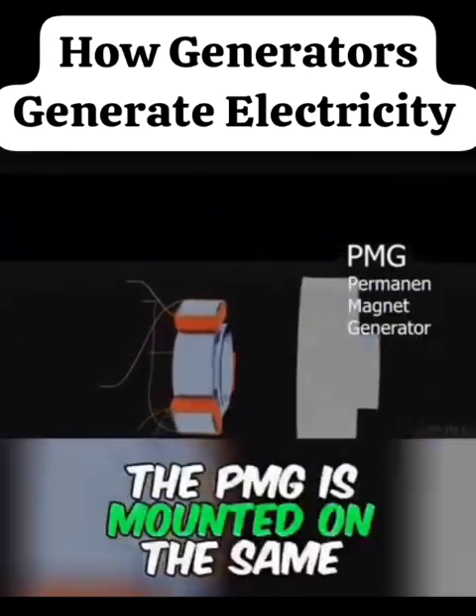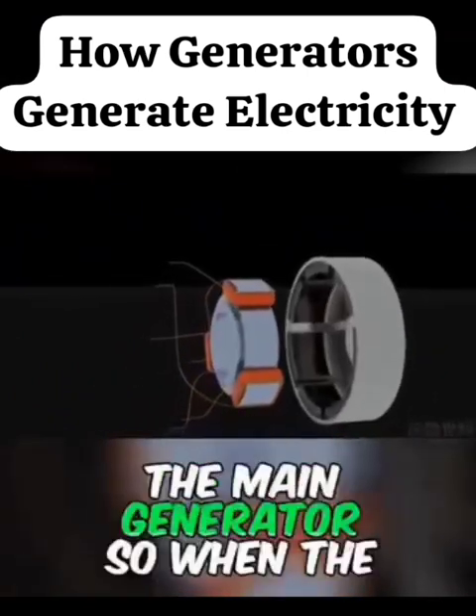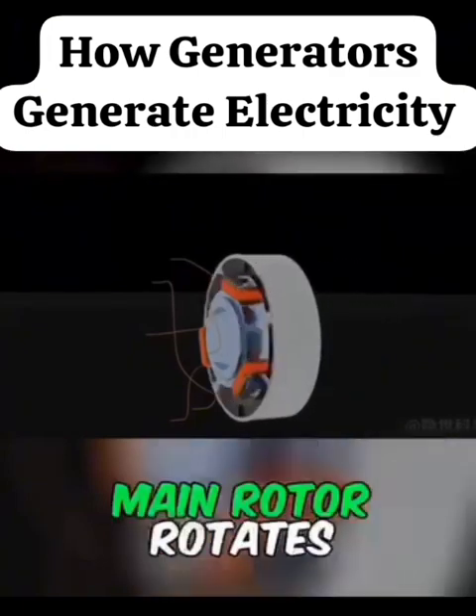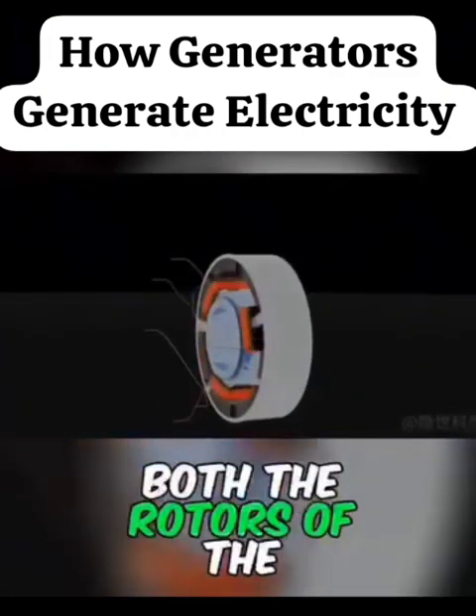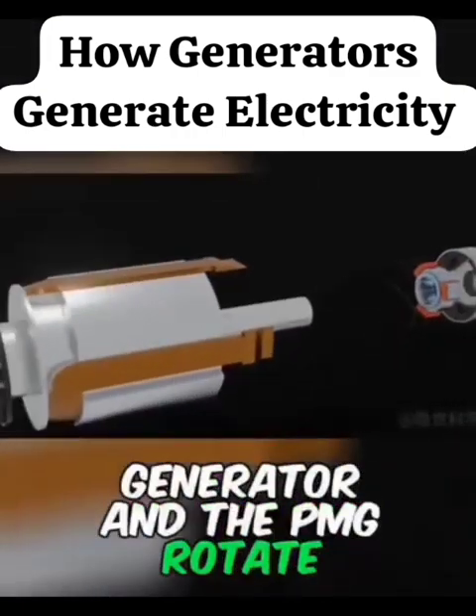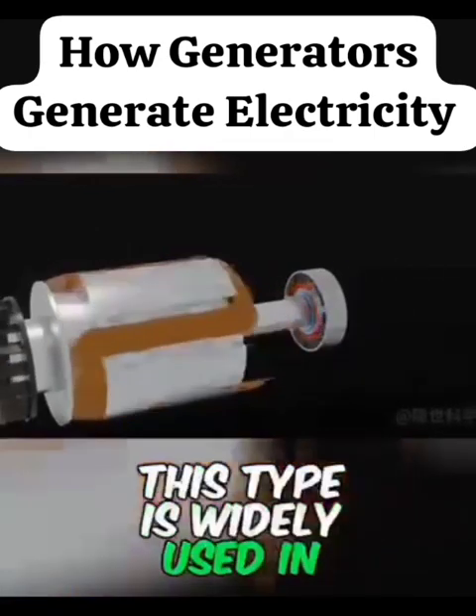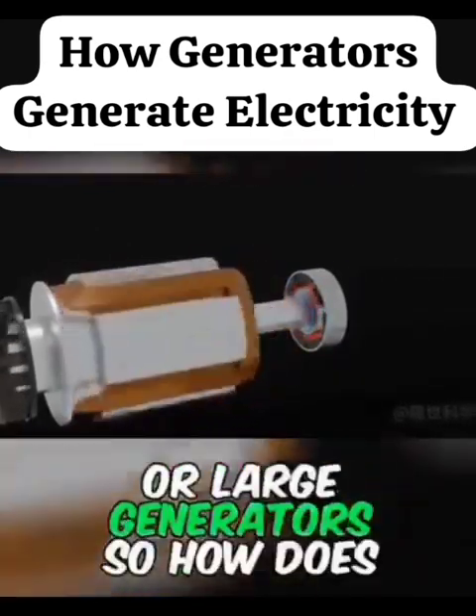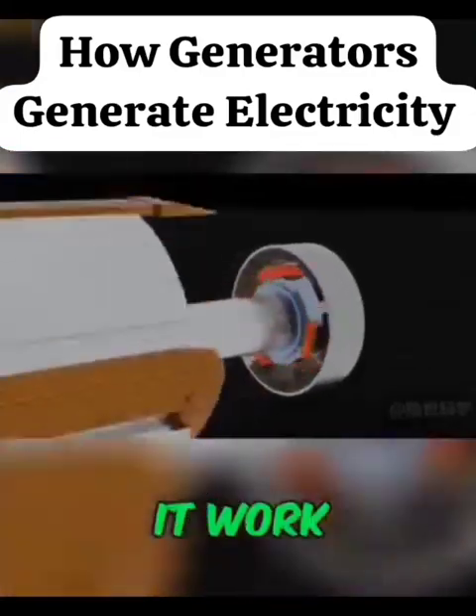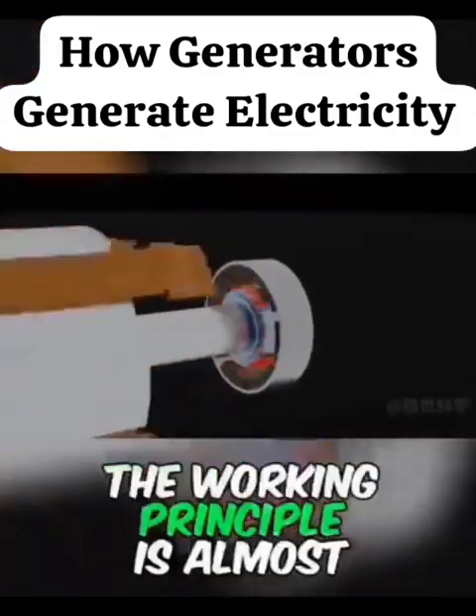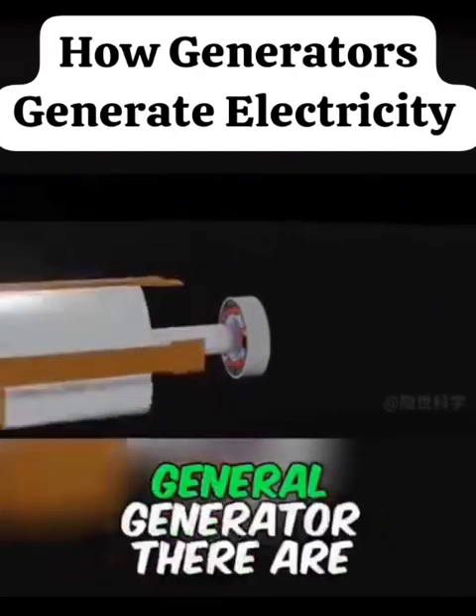The PMG is mounted on the same shaft as the main generator, so when the main rotor rotates, both the rotors of the generator and the PMG rotate. This type is widely used in generator sets or large generators. So, how does it work? The working principle is almost the same as a general generator.